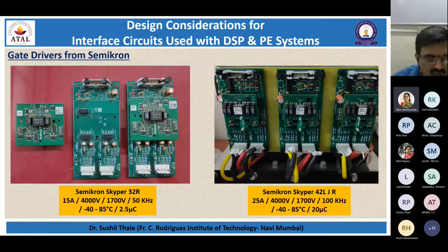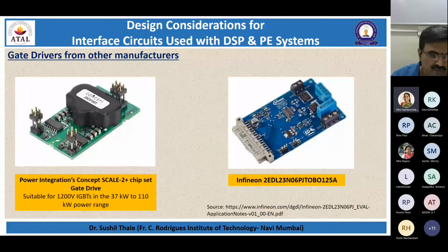These are not the only gate drivers available - let us look at other options. Power Integrations is a very popular company in the field of power electronics, especially DC-DC converters. They also produce the SCALE concept chipset gate drive, which is commonly available and reliable, suitable for IGBTs up to 37 kilowatt to 110 kilowatt power. That means they are suitable for IGBT switches that can handle that kind of power range in the actual application.